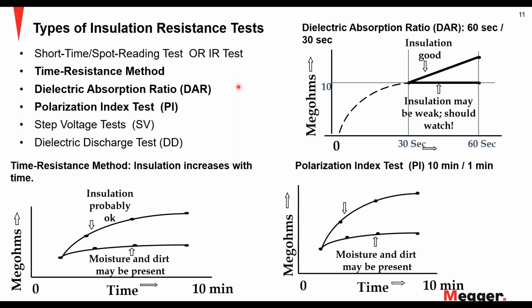Step voltage is basically if you have to say, I want to do a test at 5 kV, you just don't increase all the way up to 5 kV. You go in steps, 1 kV, 2 kV, 3 kV, 4 kV, and then you reach 5 kV. At each step, you are taking an insulation reading, and that's your step voltage test. And your dielectric discharge, that is when you are discharging it, that's when you are accounting for a curve, how the object is discharged, and that tells you a little bit more information. So that is not very common, and a lot of people don't do it. It's more popular in Europe, but it's good to know.